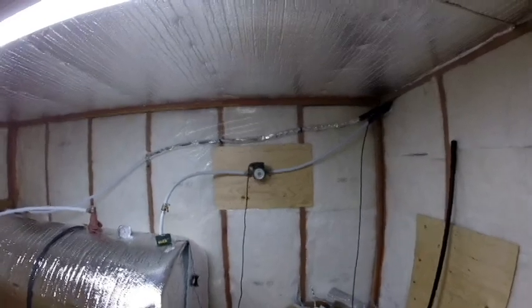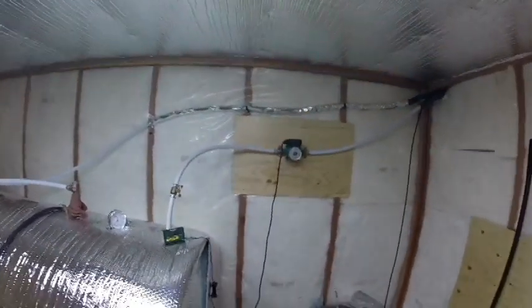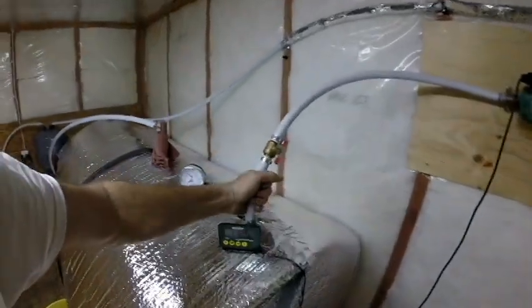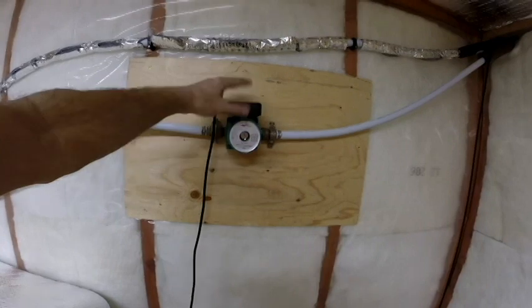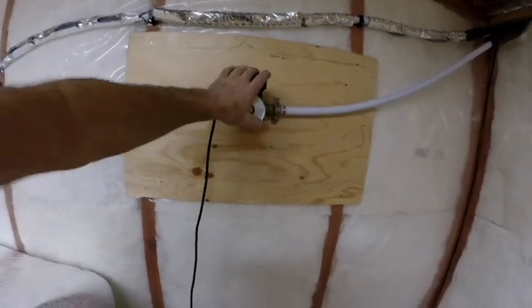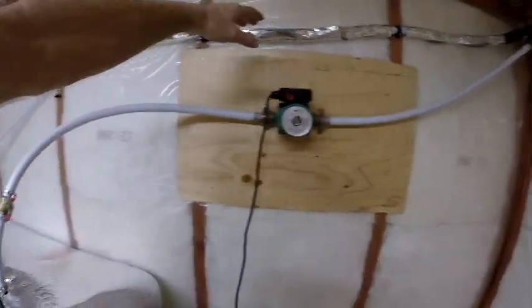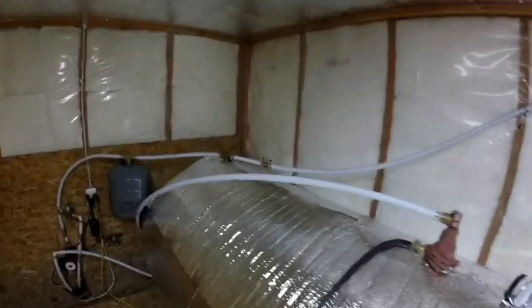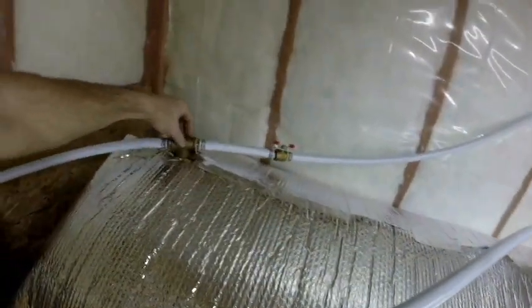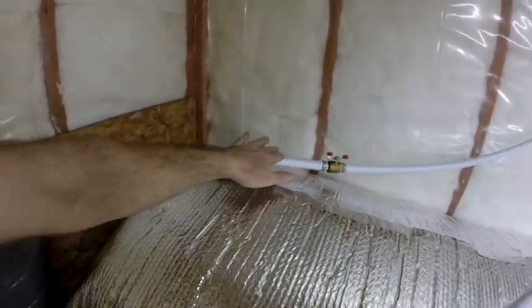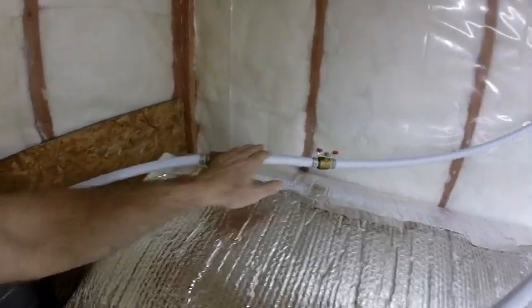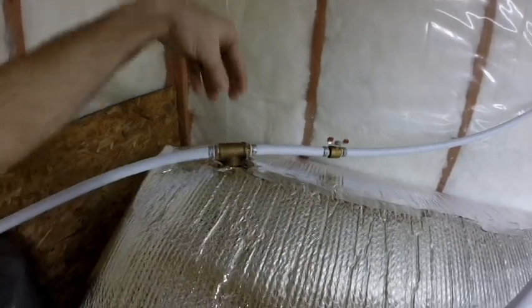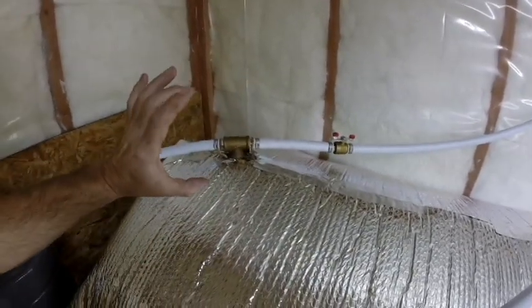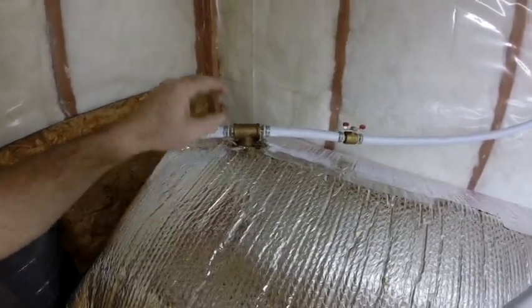There you can see I have the water pump that flows the water out of this tank. Basically, this nozzle here has an extension. The water is pulled from the bottom of the tank, comes up through here, through this pump. It's a 3-speed cheapy pump, $100 pump. Flows into the shop. Water's heated, comes back out of the shop into that line, which then flows into this T. Now, the interesting part about this T is this is output to the house. This is input from the heated water, and then this T goes into the tank, and there's a 4-inch extension off the bottom of this thing, so it pulls the water from 4 inches down and not right at the surface.